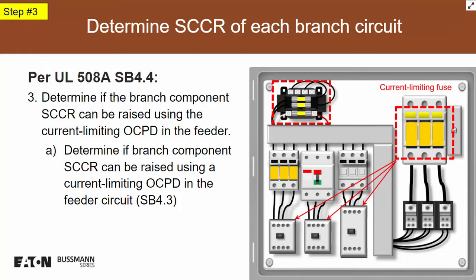But I can change the branch components, not the branch overcurrent protective devices, only the branch components. So the main fuse, in this case the current limiting fuse, can change the branch contactors, the 2 contactors, and the drive. It will not be able to change the transformer fuses at all, and it can't change any overcurrent protective device, just branch components. With that, that will help me boost up my overall SCCR for the machine or for the panel itself.